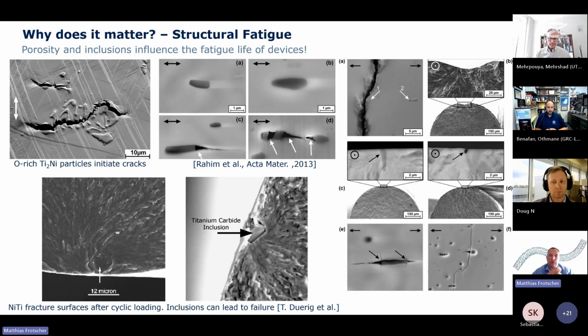They form during deformation of nitinol material, for example, when manufacturing wires or tubing, and the nitinol matrix is deformed, but the hard and brittle secondary phases break up during this process and are elongated, forming stringers in the forming direction. And in some cases, the nitinol matrix is not fully closed around the inclusions after processing, leaving these porosities close to the particles. And at the interface between the porosity and the inclusions is the highest stress location where the crack would initiate. And those cracks can connect, allowing the crack to more easily propagate through the material from one inclusion to the other.